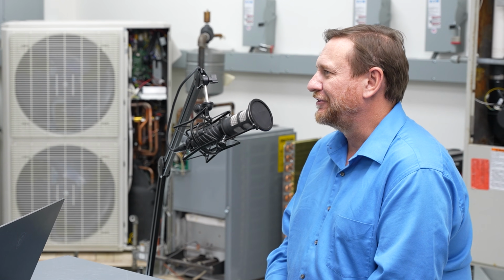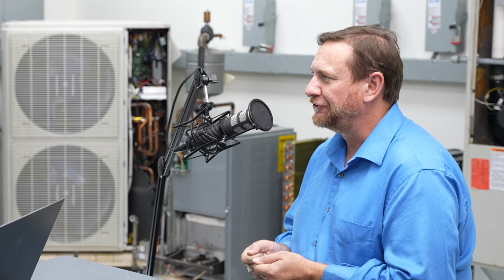You can also check those switches with voltage. While they're hooked up and operating, you can check voltage across them if you have a point to check. If it's a closed switch, you'll have 0 volts. If it's an open switch, you'll have whatever voltage you're working with. Maybe it's 24, maybe it's 120, sometimes even 240, but across an open switch you'll read voltage.